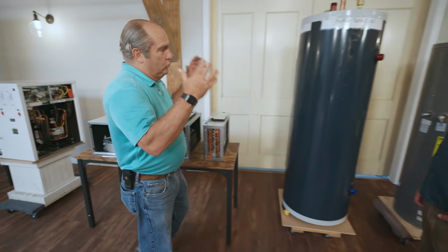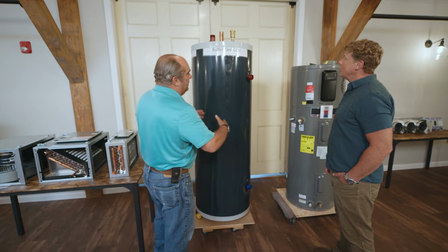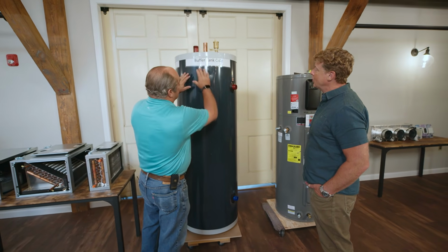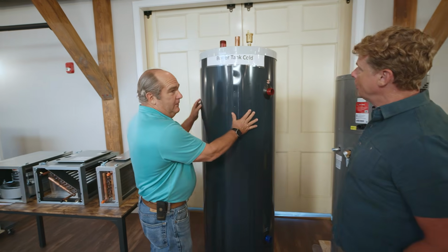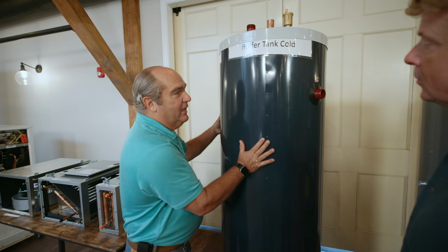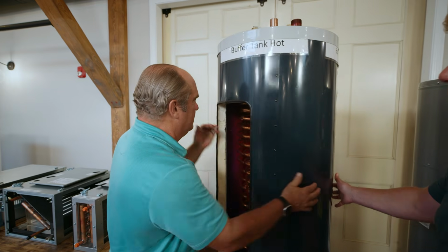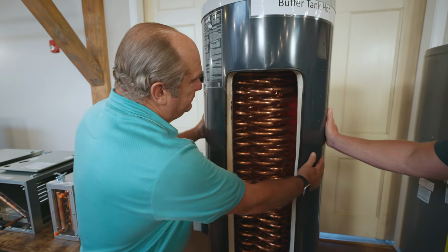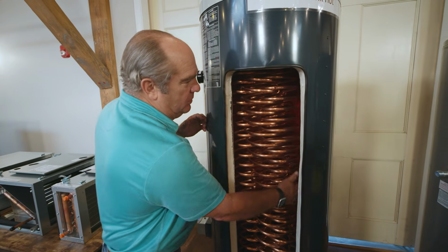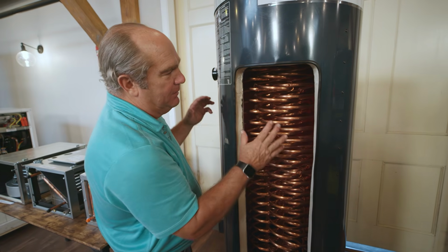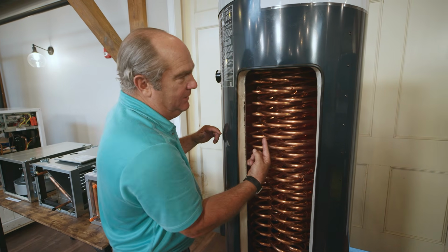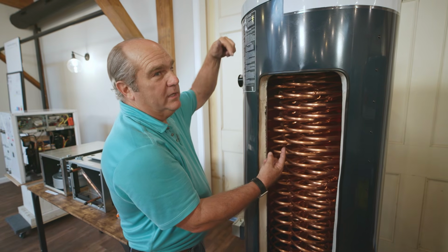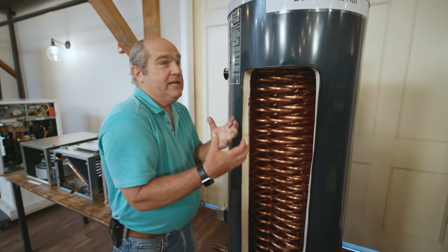And then your BTU. 2 tanks, a big blue tank and a big red tank. One's the buffer tank. They both look very similar, but the hot water tank's going to have an additional piece I mentioned. This is the heat exchanger inside of it. So now, this stores all these BTUs ready to go for the heating, but it also has coils inside of it that potable water will come through here, and it'll now come out heated.